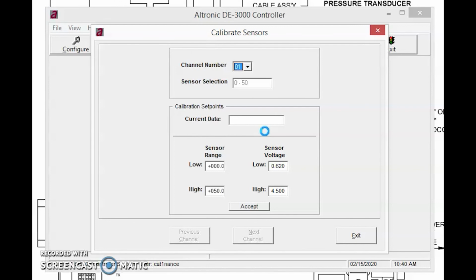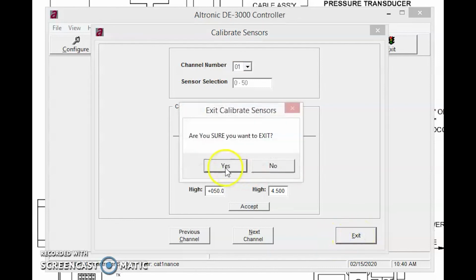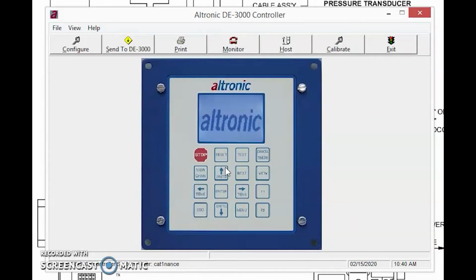Once you're completed with your calibration procedure, you can simply exit and you're done. Now those calibrations will always stay inside the DE-3000, even if you pull programs out and update programs and dump programs in. If you ever need to wipe or restore calibrations back to default, you can do that. The best way to do it is to actually load a blank program in the DE-3000 and then load your original program back into it. We'll cover that step in more videos.